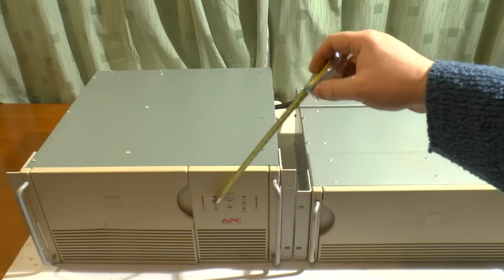And first on the dissecting table, we've got this APC SmartUps 2200XL. And this is one of the early models of the 2200XL, which, as you can see, is quite tall. It's 5 rack units high, and we've also got, as a bonus, the 4 rack units high external battery pack. The XL means it can take an external battery pack. It's got a connector on the back which will take this, and it can take several of these because this also has a connector on the back, so you can daisy chain several of these and put them on the back to get much longer run time, depending on obviously how much kit you've got running.